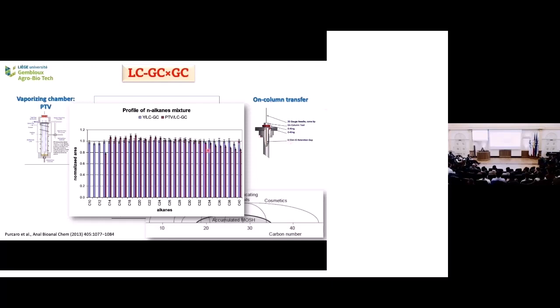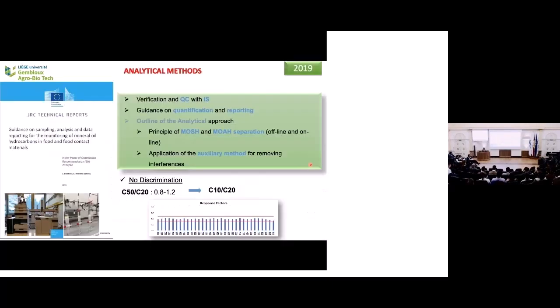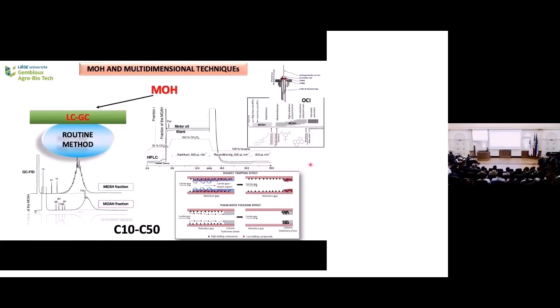Since then, all the requirements in the characterization of mineral oil contamination has changed. Now we are required to characterize between C10 to C50. In this case, the PTV interface actually failed because it's very difficult to optimize it without having any discrimination of the fraction that we are transferring. Beyond C35, we start to have a decrease of concentration of our compounds. So we need to go back to the on-column interface to meet the requirements of the European Union, the opinion of EFSA and the JRC guidance.